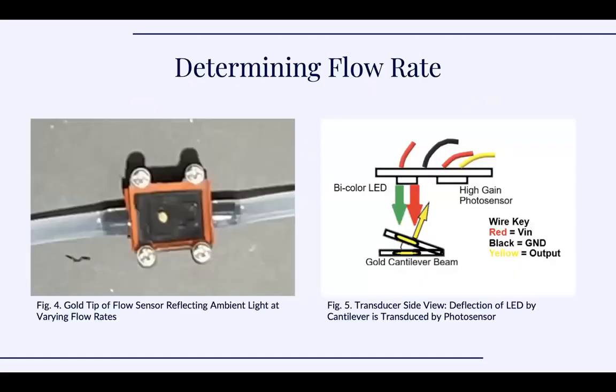As the one-way valve in the hydrocephalus shunt discharges, the cantilever beam in the sensor deflects. The changing angle of incidence from the light source increases the intensity of the deflected light onto the photosensor. This signal shows the rise and fall of the cantilever, which responds to the flow rate through the shunt.